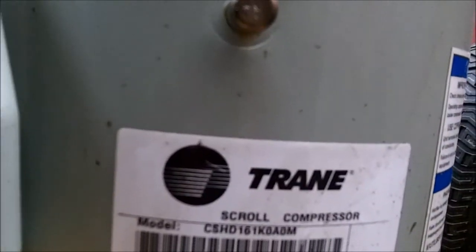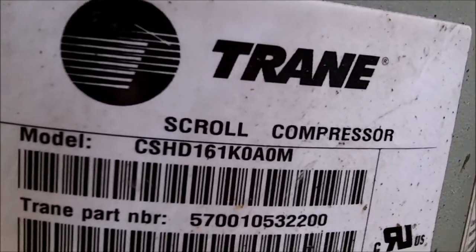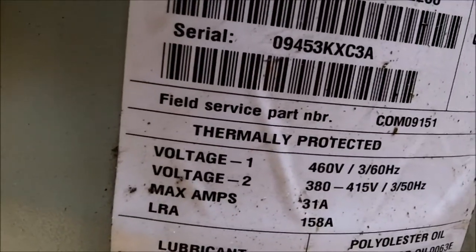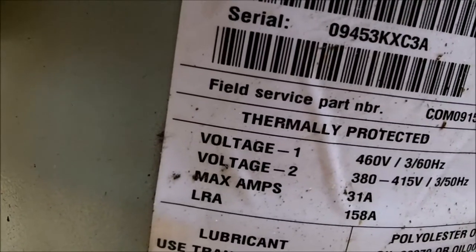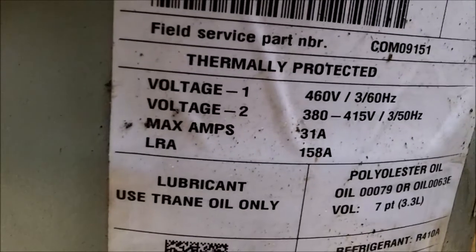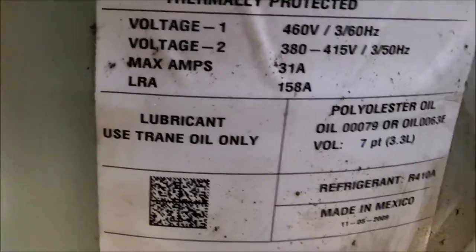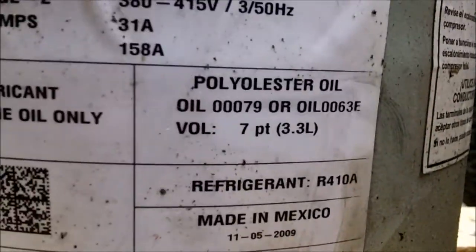The information tag reads: Trane scroll compressor. There's a model number — I'm not going to read that off, you can pause the video if you want. Voltage one is 460 volts. Voltage two is 380 to 415 volts. Max amps: 31 amps. Locked rotor amps: 158 amps. It uses polyolester oil, meant for R410A refrigerant. Made in Mexico.